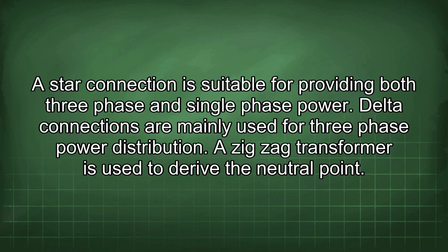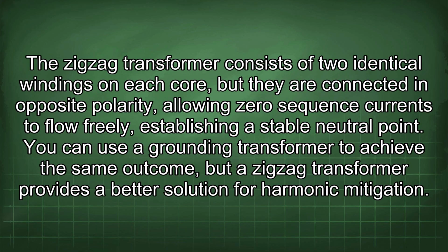A star connection is suitable for providing both three-phase and single-phase power. Delta connections are mainly used for three-phase power distribution. A zigzag transformer is used to derive the neutral point. The zigzag transformer consists of 2 identical windings on each core, but they are connected in opposite polarity, allowing zero-sequence currents to flow freely, establishing a stable neutral point. You can use a grounding transformer to achieve the same outcome, but a zigzag transformer provides a better solution for harmonic mitigation.